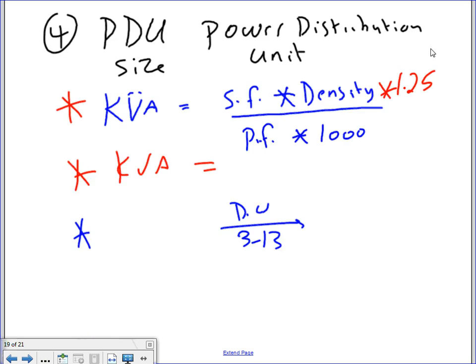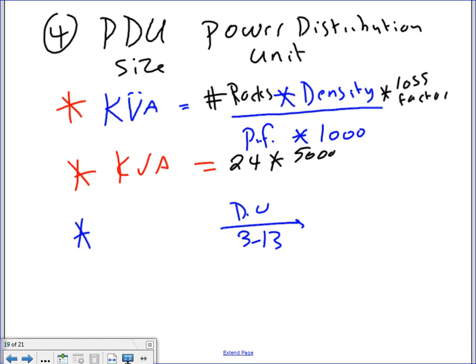All right, so let's go next. PDUs. For the PDUs, do me the same favor, gentlemen. For the PDUs, we're going to change this formula here into loss factor, and I will change it from square foot into what? Number of racks. Okay, so do me a favor. It was 24 racks multiplied by the density. Should I do the 5,000 now, just to play with that one? Here's the 5,000 watt times the loss of 1.1 divided by power factor 0.9 multiplied by 1,000.